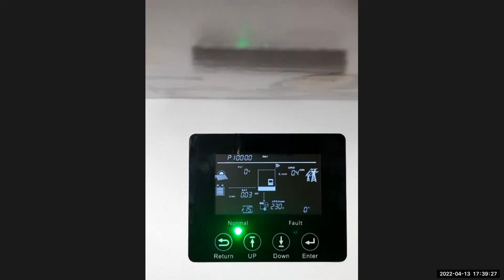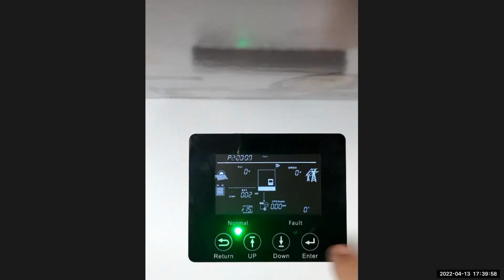Number 15 is AC first. AC first is when this unit will only use battery power, will only use Eskom to provide the load, even if there's sufficient panels. So AC first is only for a backup system. That means there's no panels and only batteries for when Eskom goes out. It's basically running as only a backup system. If you don't want it to run as a backup system, it's 0, 0 at all the settings. If you want it to run as a backup system, 2359 at P1. And then basically it will always use Eskom as far as possible to provide your loads.